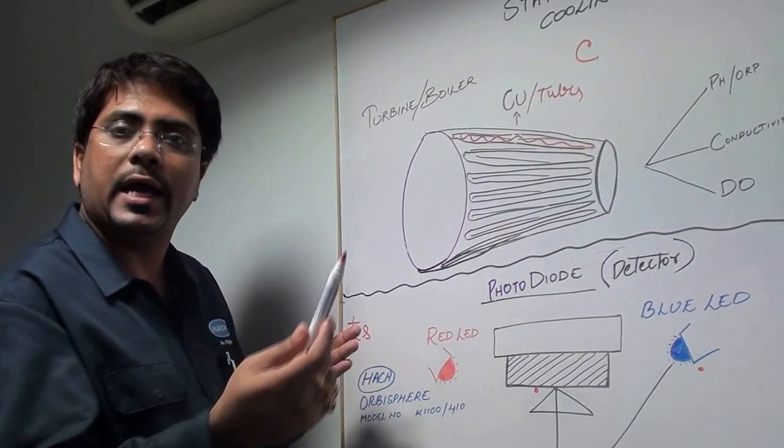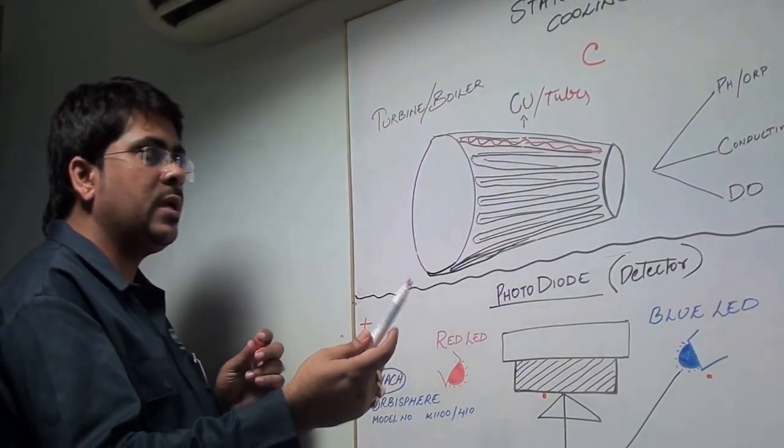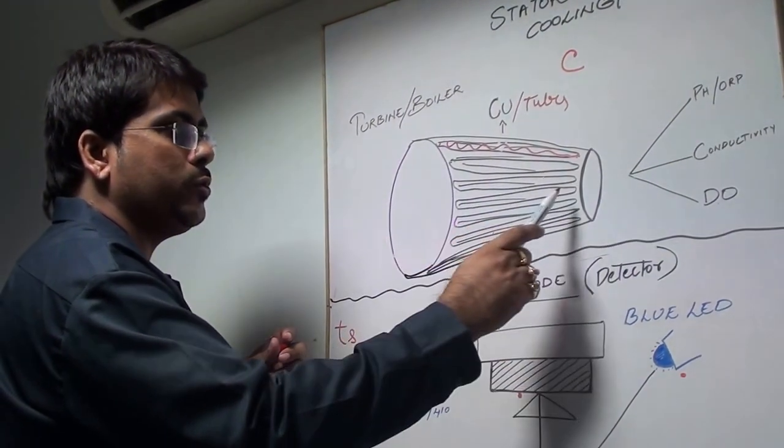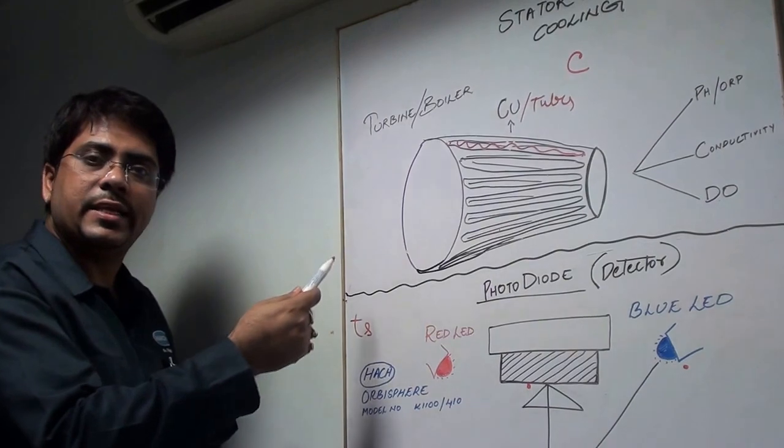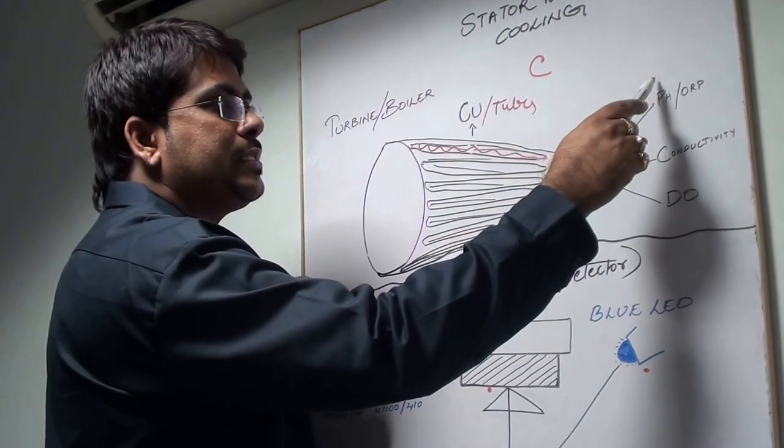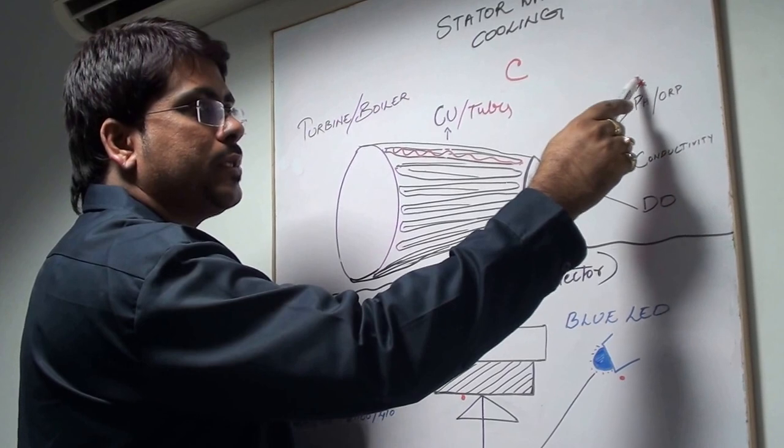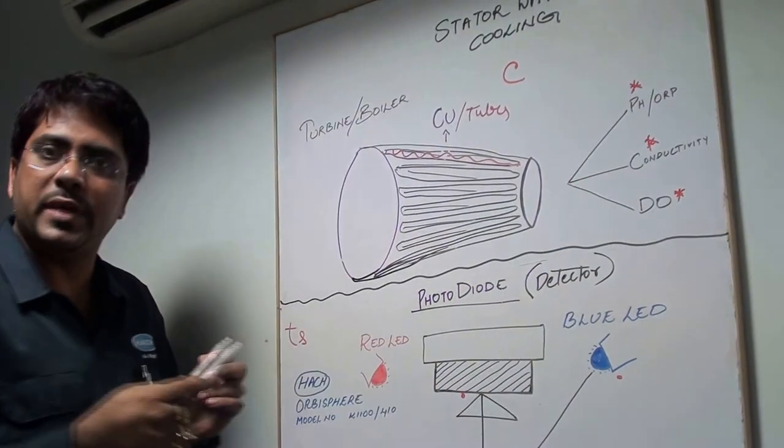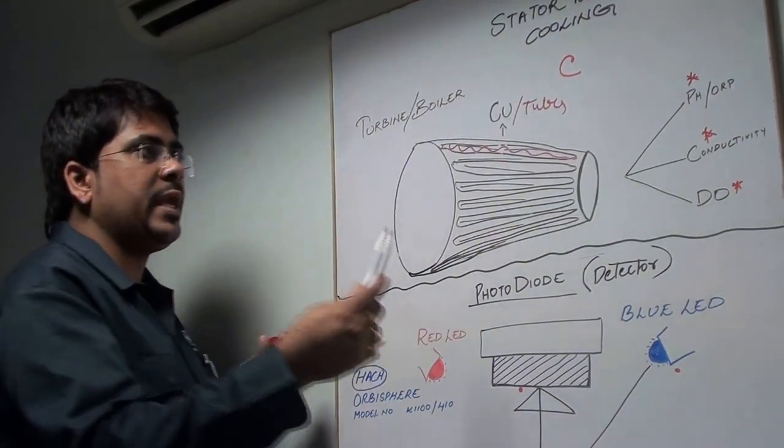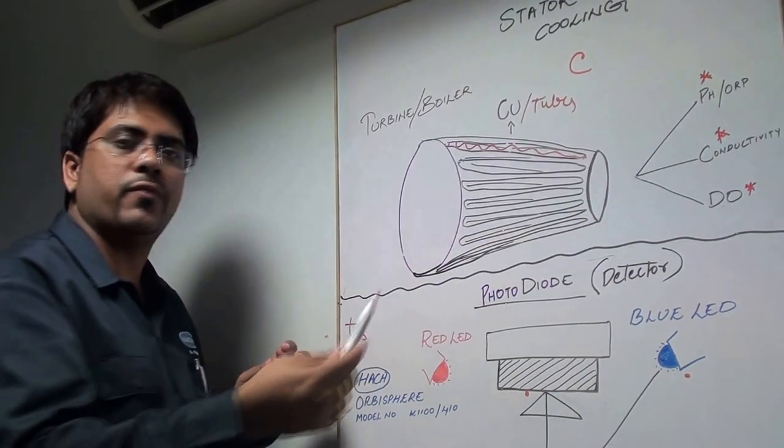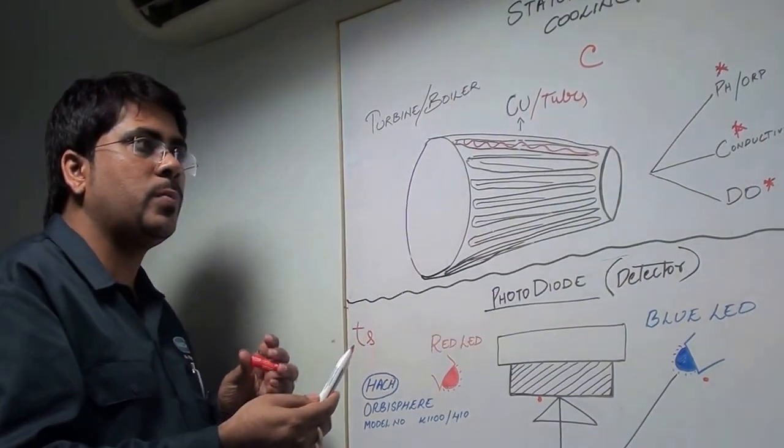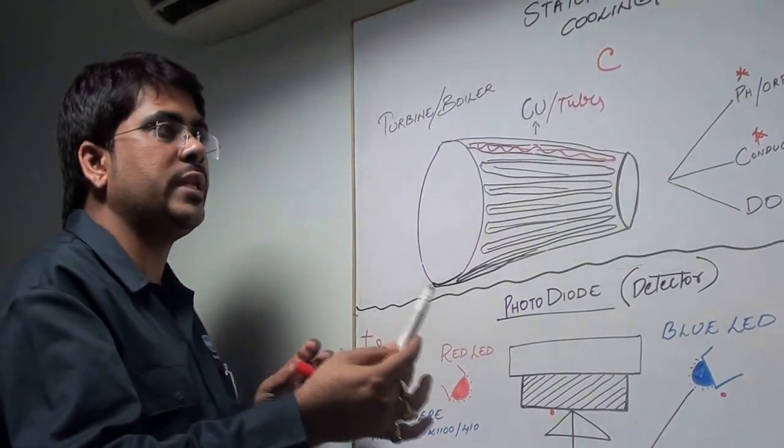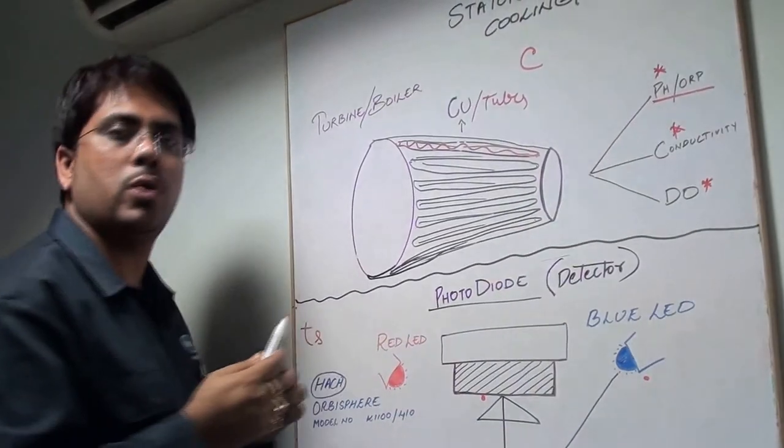When this ultra-pure water flows through these tubes, at the inlet we should definitely measure three particular parameters: pH/ORP, conductivity, and dissolved oxygen. pH and ORP are measured to detect whether the water going through this tube is becoming acidic or alkaline in nature.